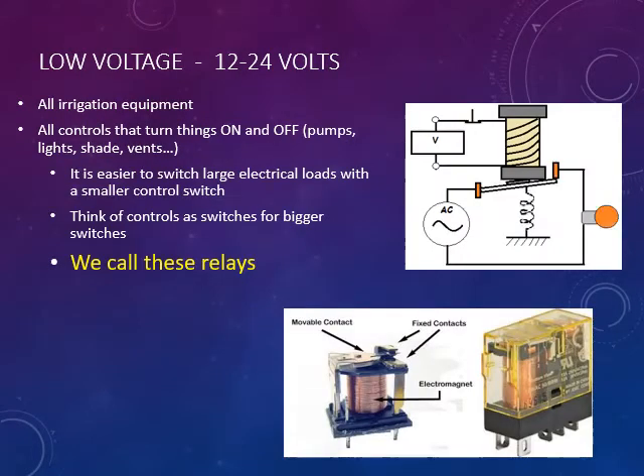How does a relay work? I've got an animation here that's pretty helpful. Essentially, what we have is a 24 volt power supply, 24 volt AC. When you make contact, 24 volt AC flows through this coil and back around the other side. It can go this way, and then it can flip and go the other way, it doesn't matter, it makes a magnetic field. This coil pulls this metal plate in, so this plate gets attracted to the coil, which pulls the plunger up, meaning this high power circuit is then switched and current flows through this light bulb.